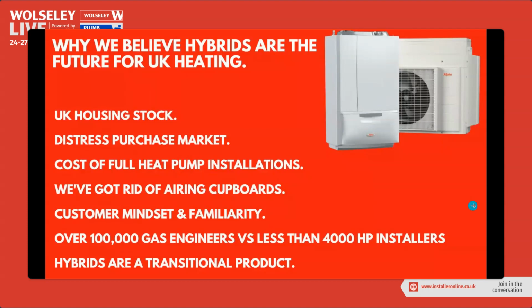The next point is customer mindset. Low temperature heating takes some getting used to - the days of walking in, whacking the thermostat up and the house being warm in 20 minutes are long gone with full heat pump systems. We have to operate at a lower temperature, which means having the heat on for longer, and looking at introducing a setback temperature so we maintain the thermal mass of the building.